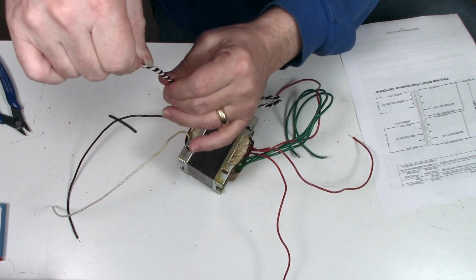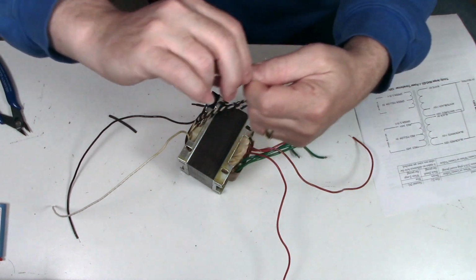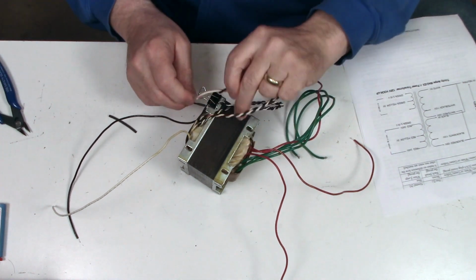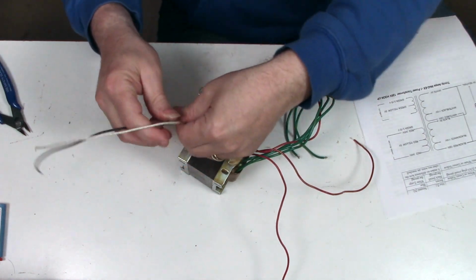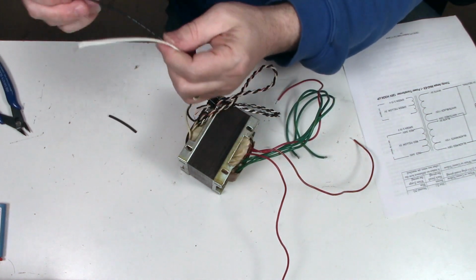So that's the red-black and red-white wires, now wound together. For the supply side, the last two to wind together are the black and the white. It can be hard to see the red stripe on the black wire, and I have made the mistake in the past of getting those two switched. So I want to make sure I have the solid white and solid black together, and the black-red and black-white together. So measure twice, cut once.